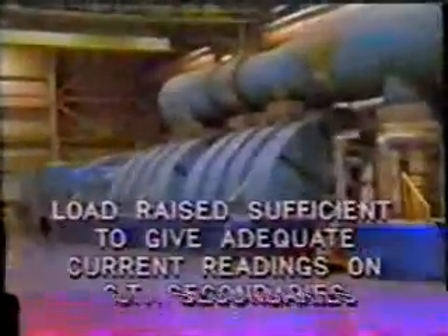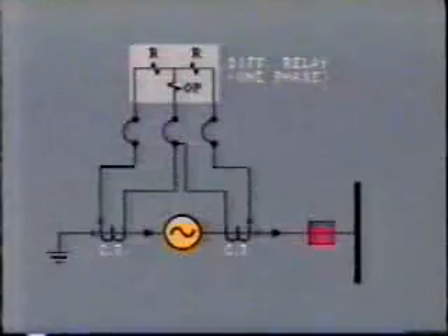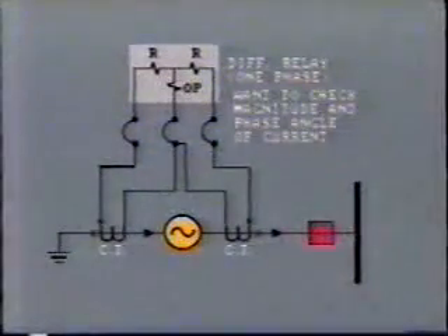Once the generator is paralleled to the bus, load on the turbine generator can be raised sufficient to give adequate current readings on the CT secondaries, and so allow in-service readings to be taken at the CT links. As an example, let's look at in-service readings of the generator differential protection taken at the relay panel. Our objective is to test the magnitude and phase angle of current in each of the restraining coils and operating coils. A suitable ammeter and phase angle meter are connected to the circuit under test through the test board.